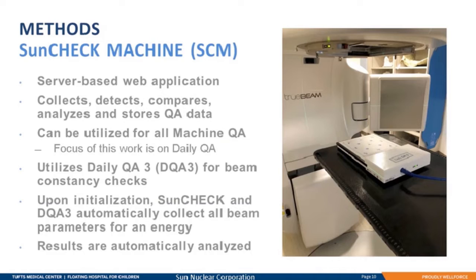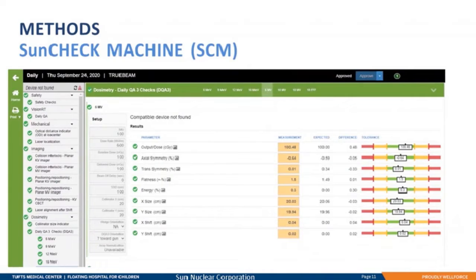In our clinic, SunCHECK machine integrates with the daily QA3 Phantom from SunNuclear for consistency checks of various beam parameters. When initialized, the data is automatically collected, analyzed, and saved. Immediate feedback is provided to the radiation therapist on the results of the test. Here you can see an example of a set of dosimetry results using the daily QA3. All parameters with the same energy are collected with one beam measurement and compared against a baseline measurement. Results are automatically displayed with both visual color cues, measurement values, and tolerance displays.